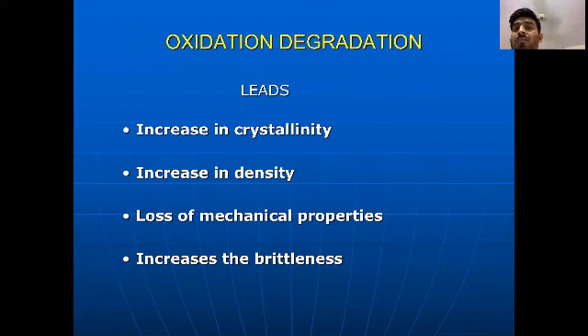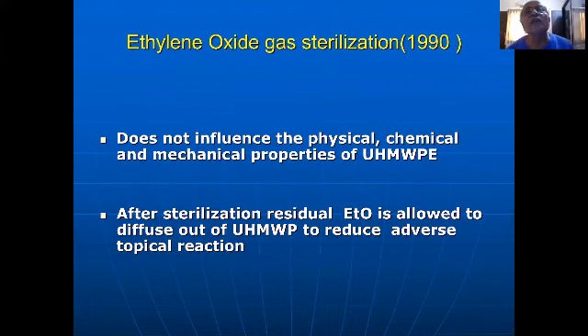So the other possibility was, instead of that, ethylene oxide gas sterilization. This can also be used. A lot of companies do ethylene gas sterilization. It does not influence the physical, chemical, and mechanical properties of this material. After sterilization, there is a residual ETO which you allow to diffuse out to reduce the adverse effects. So you can't use it today if it is packed today; tomorrow you can't use it. You keep it on the shelf for at least a couple of weeks until the ethylene oxide gas gets diffused. So it is another way: either you do it under this, or you do it under ethylene gas sterilization.